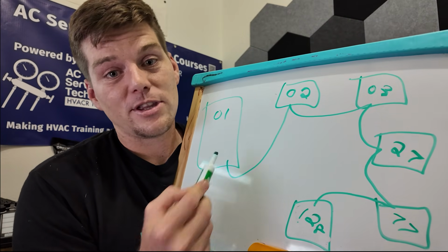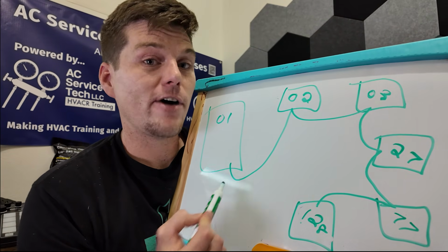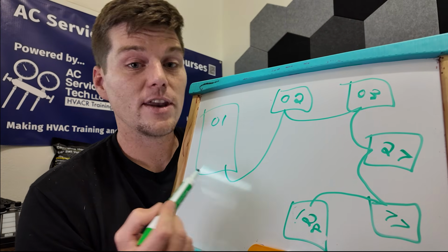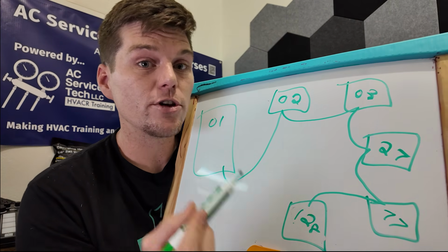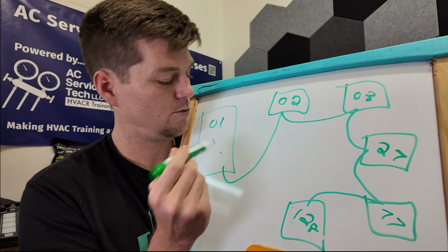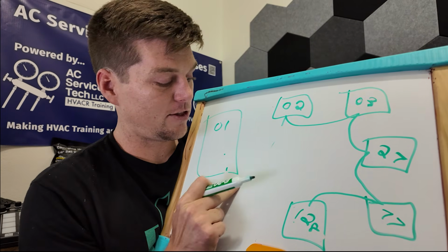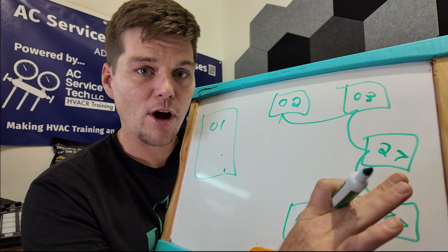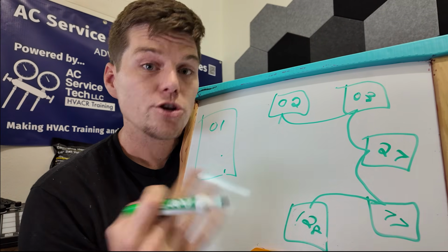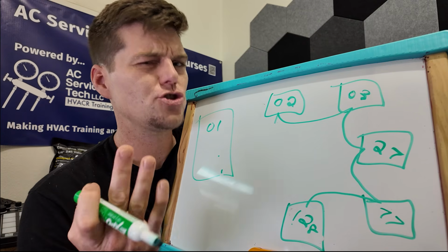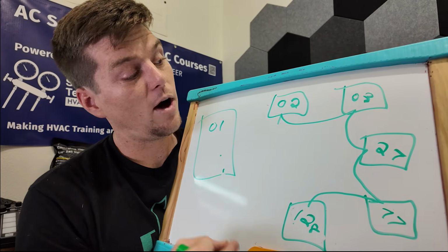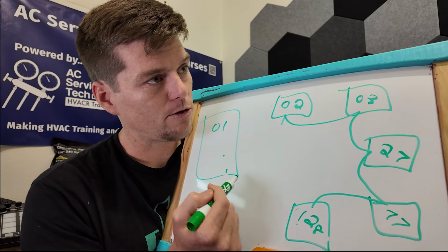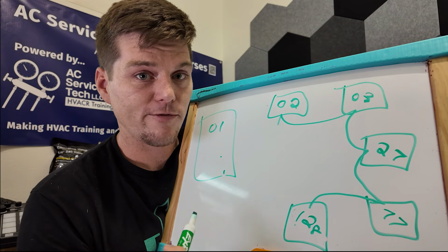So we're measuring voltage at the outdoor unit. If you don't have 16.5 volts DC at the outdoor unit, then the next step is to remove the communication wires from the outdoor unit. We want to disconnect this circuit here and say, okay, hey, I get it. The indoor units are the problem. You're good to run. Show me that you're good to run. Show me the money here. So you disconnect the wires. Maybe you do a hard restart because the voltage doesn't come back right away. Hold down the reset button. Now I'm measuring 16.5 volts DC.